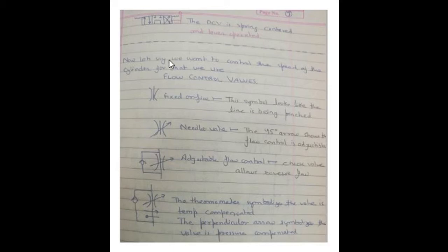Now let us see we want to control the speed of the cylinder. For that we have to use flow control valves. The first symbol is fixed orifice. The symbol looks like the line is being pinched. The second symbol is needle valve. The 45 degree arrow shows flow control is adjustable.